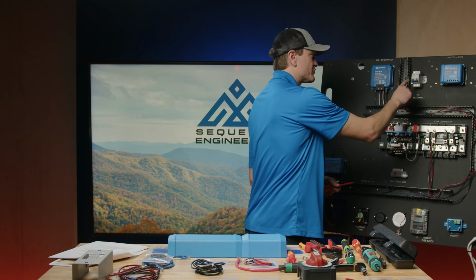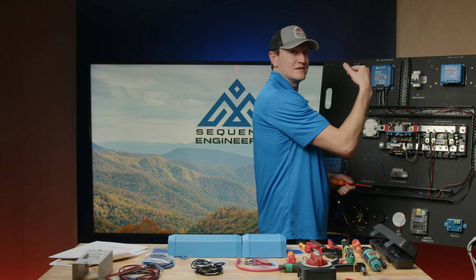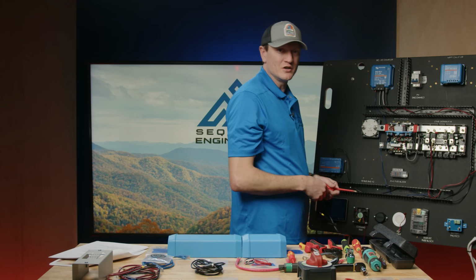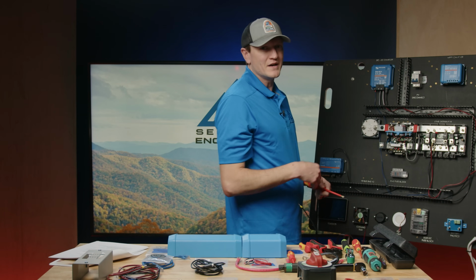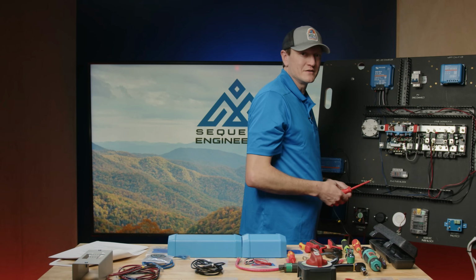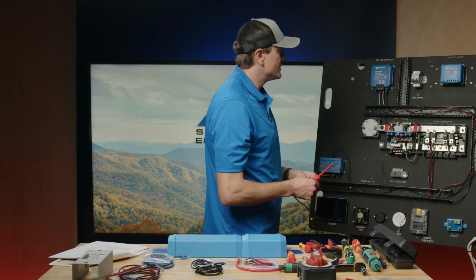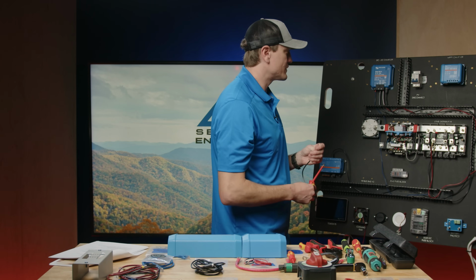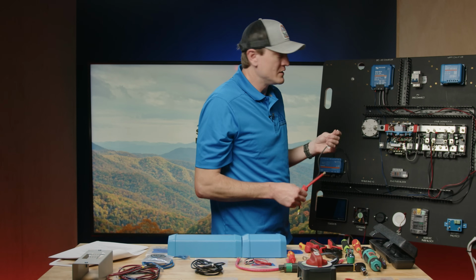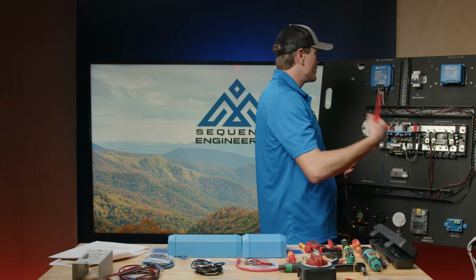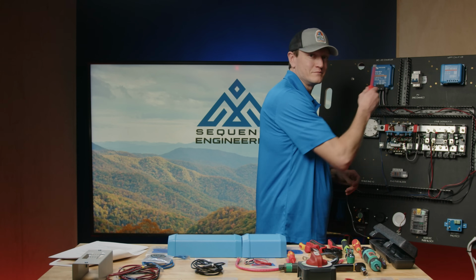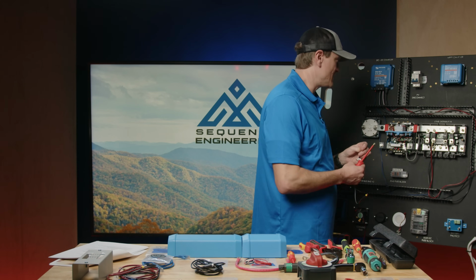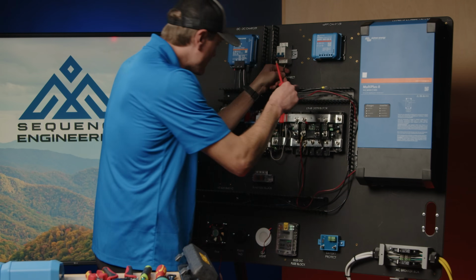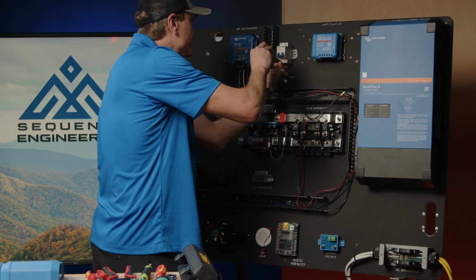This will trip at 16 amps. This is a very cheap Amazon version of a PV disconnect. You may decide you want a higher end device for this application, but we've used these in several applications that have worked quite well. If you need some type of UL cert or other certification, be sure to include that in your design. So the negative cable goes in the bottom - we're going to snug that up.